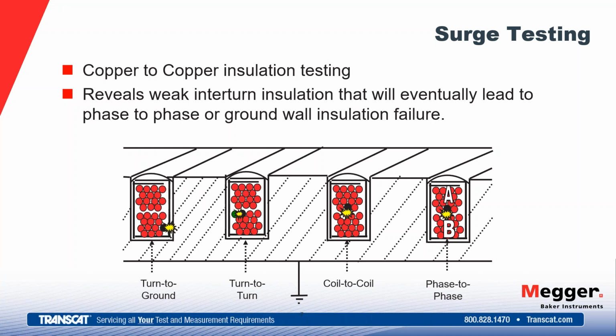This is where we find the beginning of the end of that motor, in that turn-to-turn insulation during the surge tests. So surge testing is going to cover the 3 failure modes. Turn-to-turn, so 2 turns within the same coil. Coil to coil, that would be 2 turns in different coils within the same phase. Or a phase-to-phase failure, which is a much greater catastrophic failure that we're wanting to avoid.